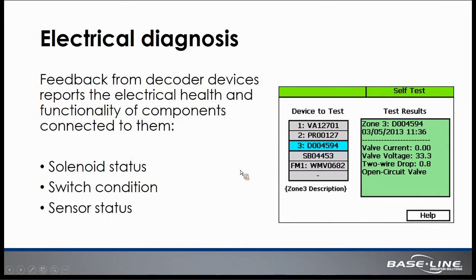One of the maintenance advantages to two-way communication is that feedback from decoder devices can report the electrical health and functionality of components connected to them. So we can get a status of a solenoid, we can get the condition of a switch that may be operating a component on the irrigation system, and we can also get sensor status, whether it's a flow sensor or a moisture sensor or a temperature sensor. And that information, diagnostic information, comes back into the controller and is viewable by the user to monitor an irrigation system.